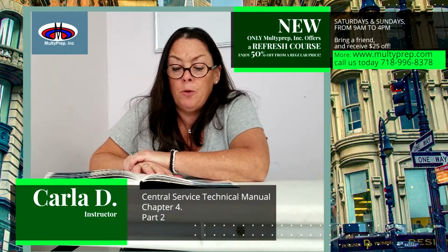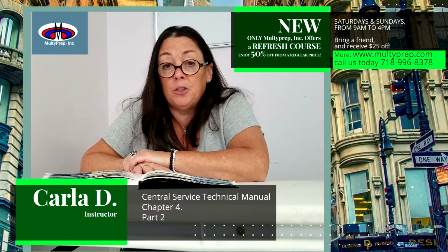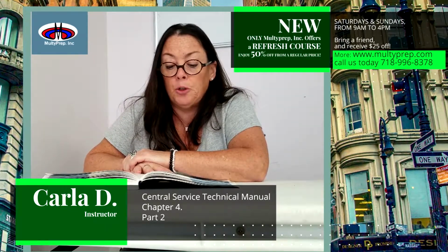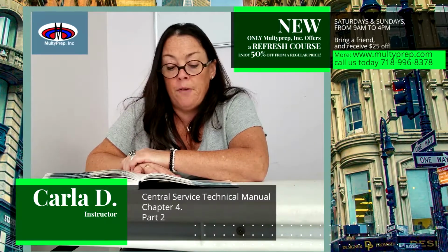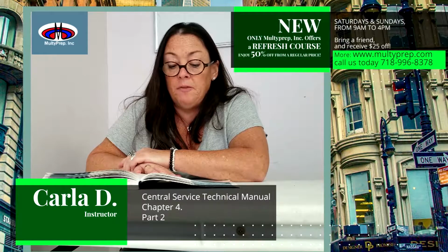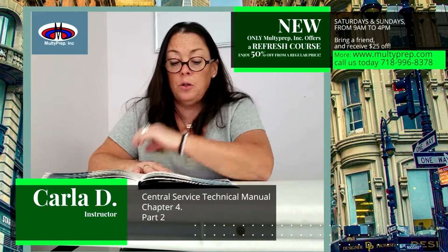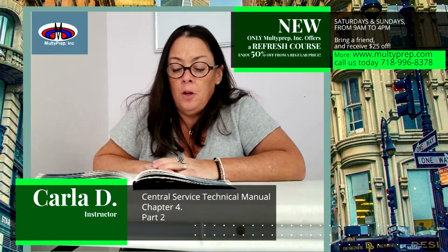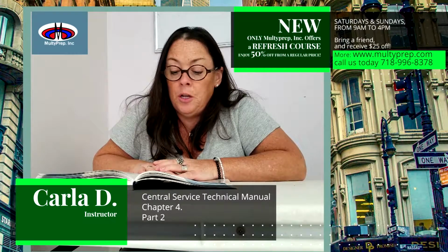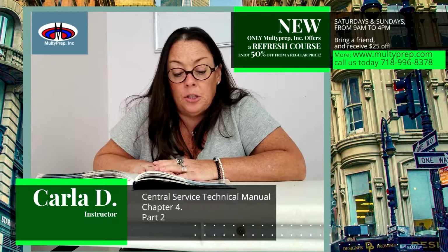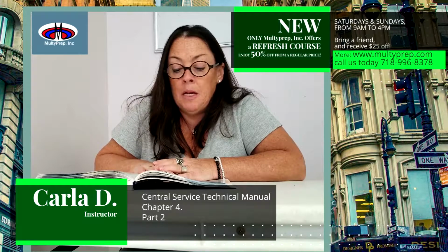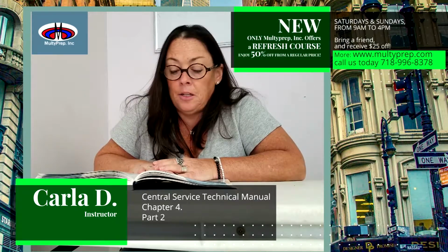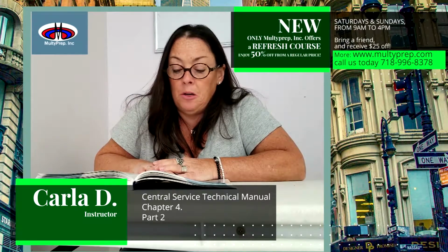Prion-contaminated instruments pose a special challenge to CS professionals. Careful attention to the most current published guidelines for cleaning and sterilization is the most important factor for your safety and the safety of patients and co-workers. Additional note: additional information about CJD can be found on the World Health Organization and SHEA, Society for Healthcare Epidemiology of America, websites, and in AAMI ST79, Annex C, and from the CDC website.